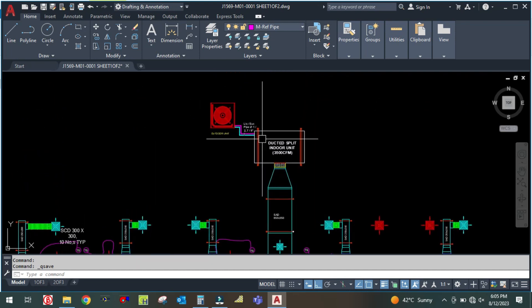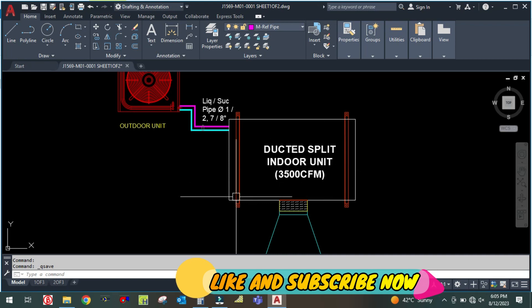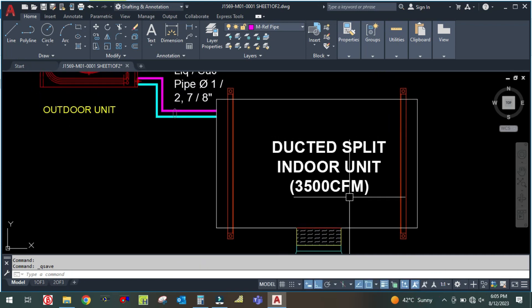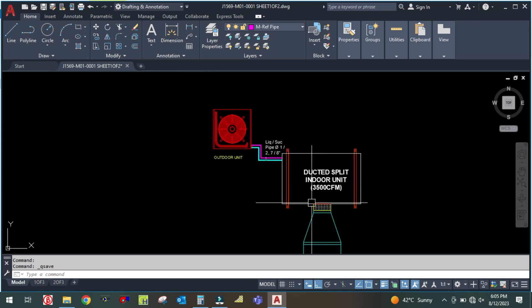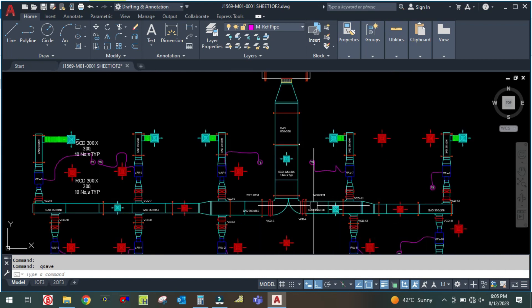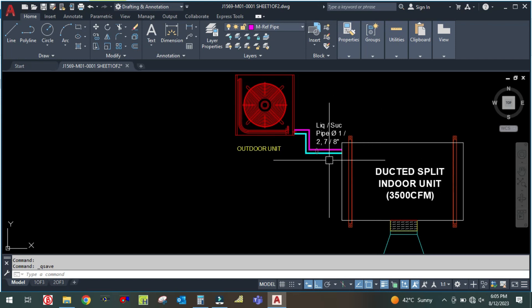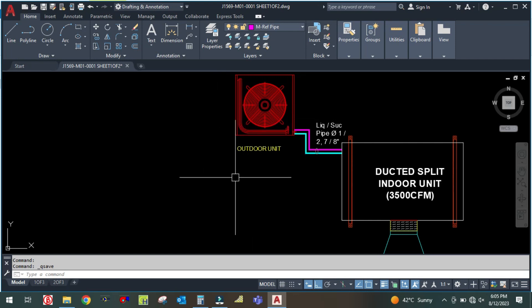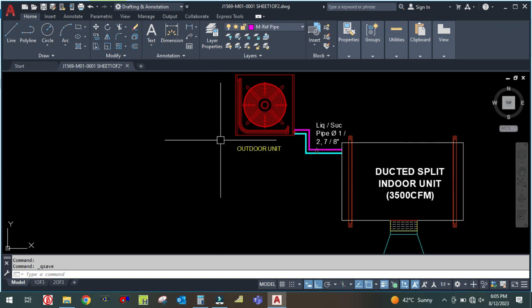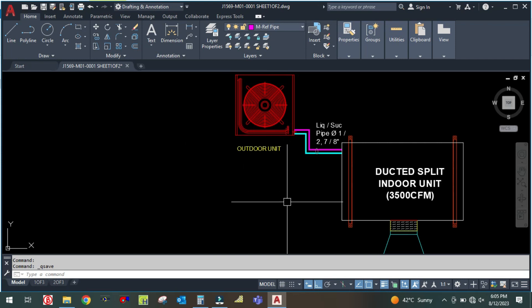As you can see, this is the ducted split AC unit — this is called the indoor unit, and it can be installed inside the ceiling, inside the false ceiling. The CFM for this machine is 3,500 CFM. CFM, cubic feet per minute, is the unit of airflow. This is the outdoor unit for this machine, and both machines are connected with refrigerant piping, which is why it is called a DX unit — because this machine is directly connected with the outdoor unit.